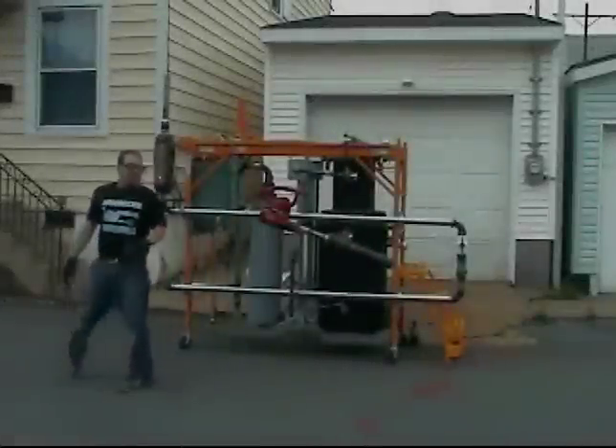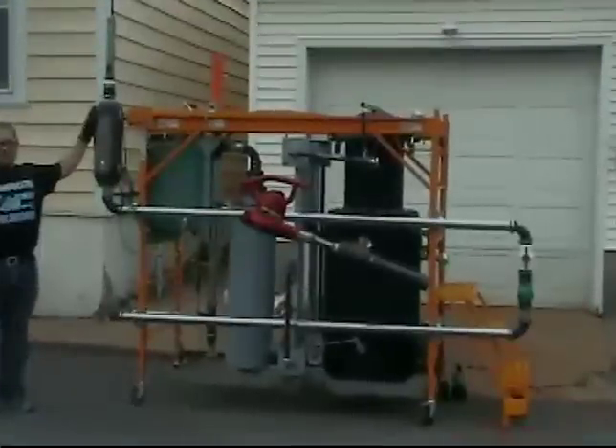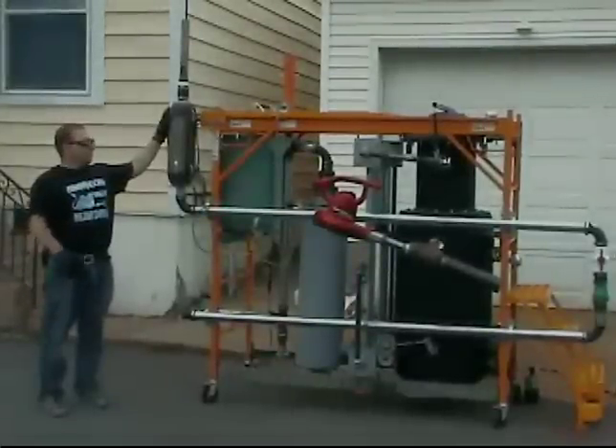Alright, if you want to pause it out, we're going to get ready to dump some fuel in here and light this thing up. What we're going to do here is fire up the blower. Before I do, I'll explain what you're going to see. I'm going to read off the numbers of what it's showing. Now, there's no fuel in the system yet. I just shut the lid down to get a reading before there's any fuel in here. And we're going to run it full blast.